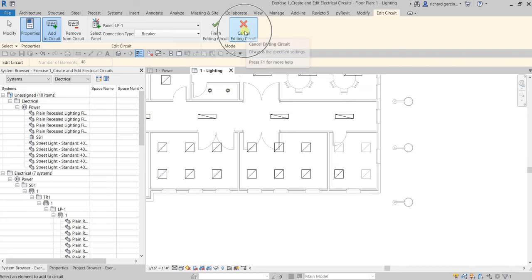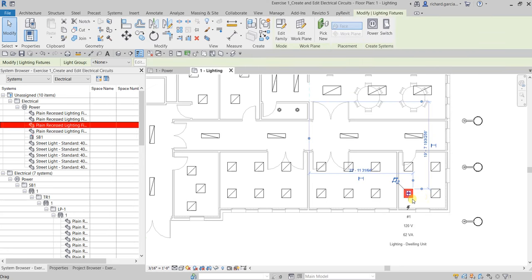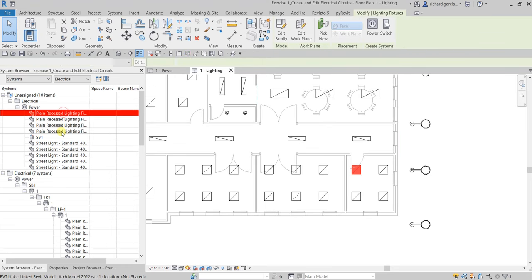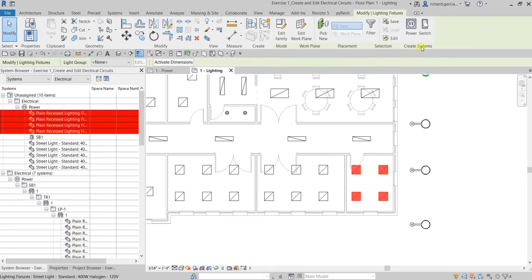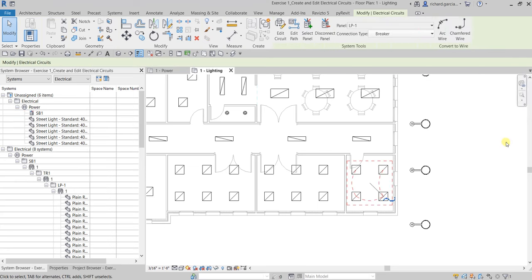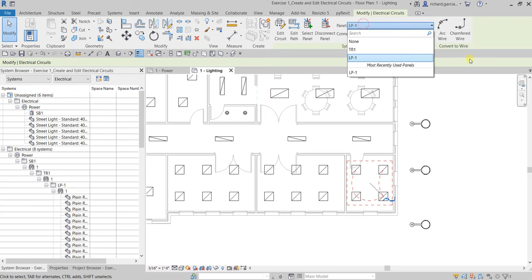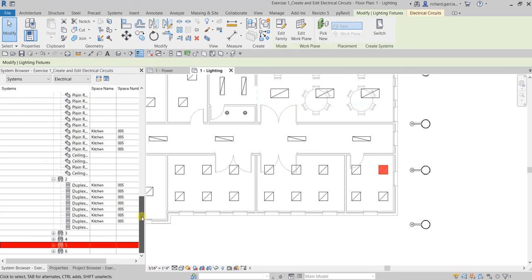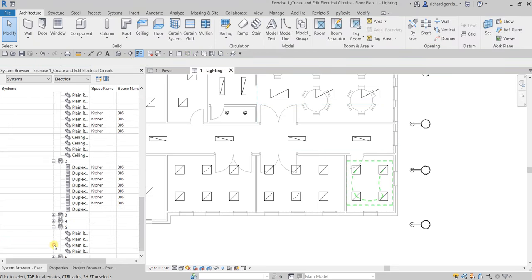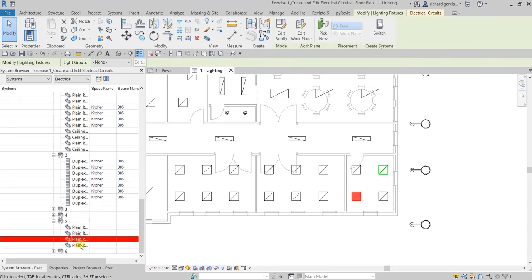Since the lighting fixture is still unassigned, we need to create a new circuit for it. Select the unassigned lighting fixtures either from the System Browser or from the floor plan, then go to Create Systems and click Power. Assign this new circuit to LP1, click Modify, and clicking one of those fixtures now shows it's assigned to circuit number five.